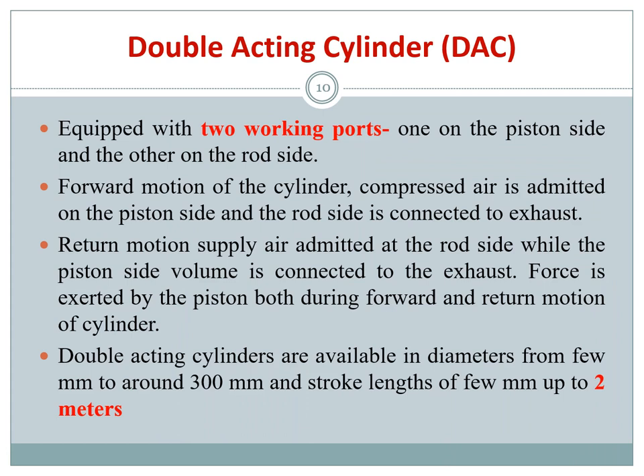Now we look at the double acting cylinder, or DAC, compared to the single acting cylinder, or SAC. In a double acting cylinder there are two working ports instead of one. There is no spring — to extend you supply air at one port, and to retract you supply air at the opposite port.